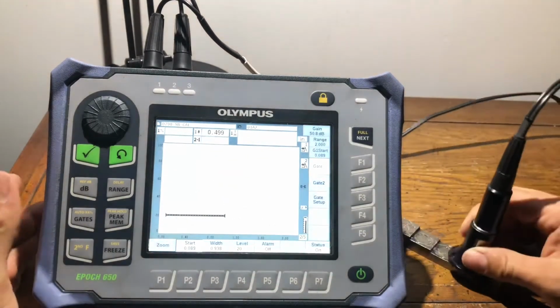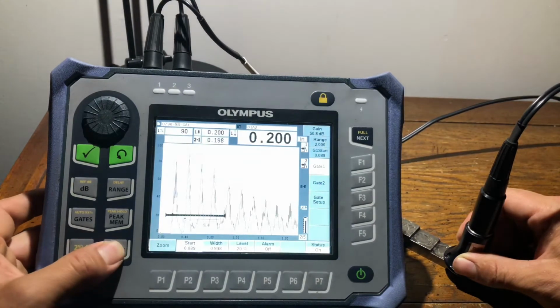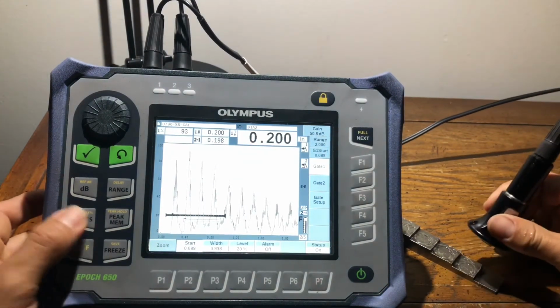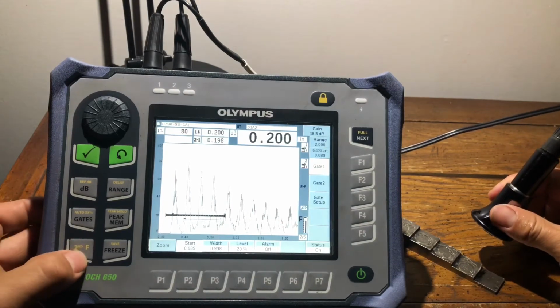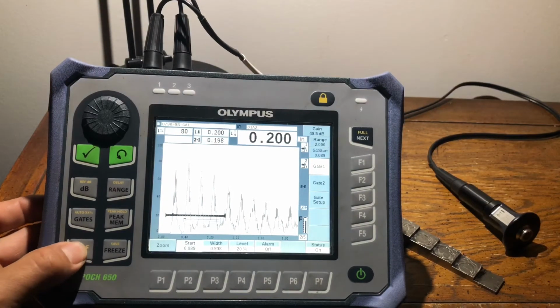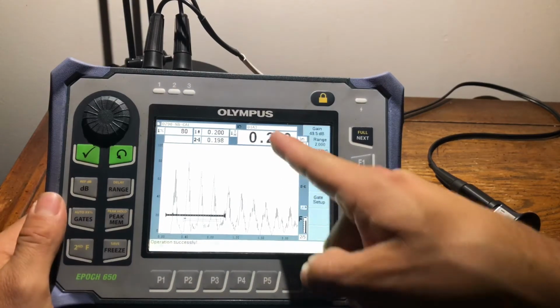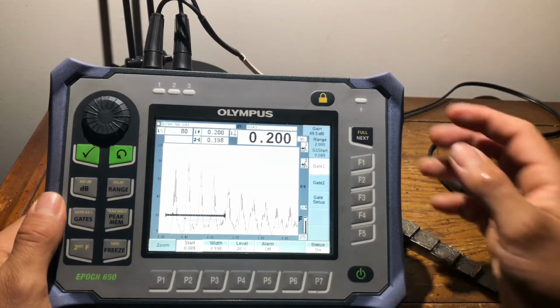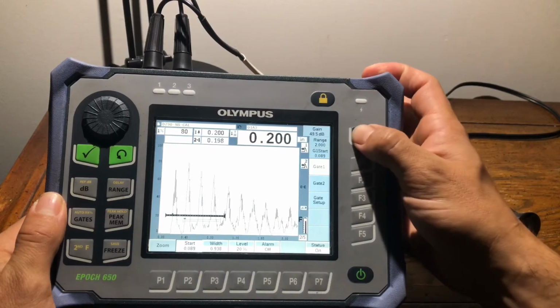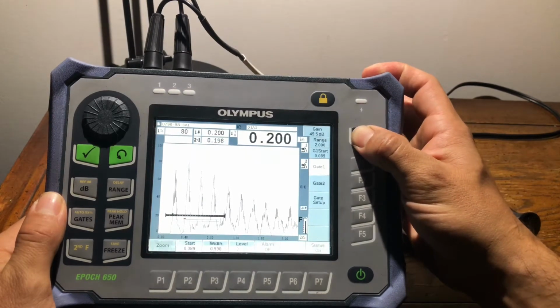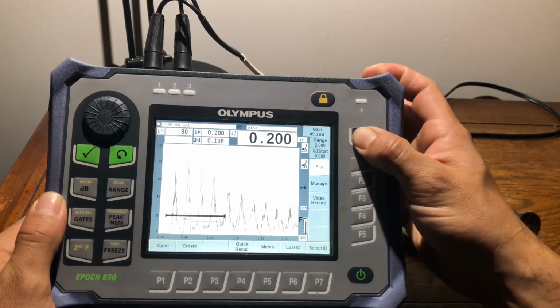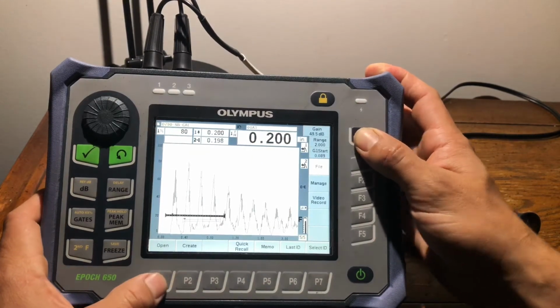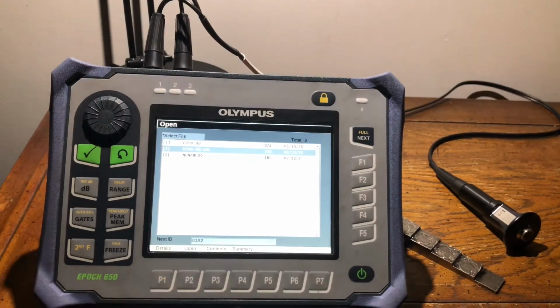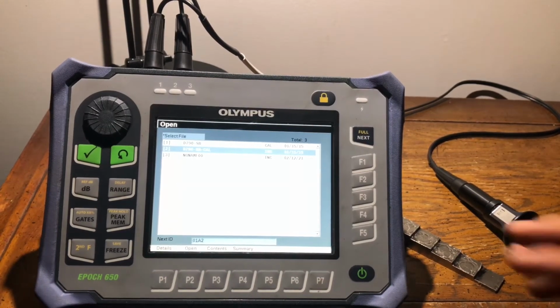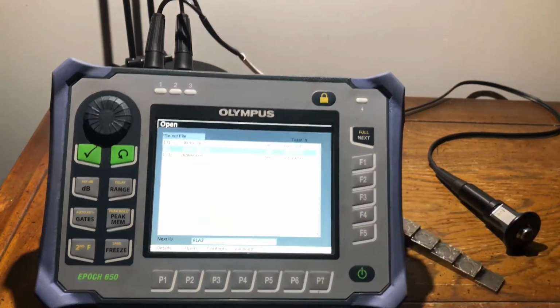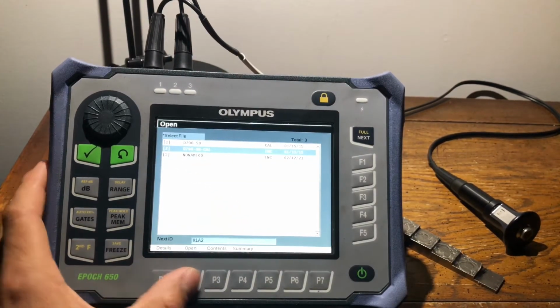You can see we're pretty close to being perfect, so I'm happy with that. I'm gonna hit freeze and auto 80 it. The way we save that in our file is real simple. You hit second function, save. As of right now, we are saved there. One last thing, just to show you guys that our files were properly saved: we're gonna hit open. We're gonna recall the calibration that we saved, and select the file that we created, the D790 straight beam cal. And then we're gonna hit content.